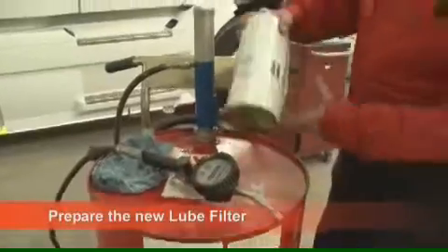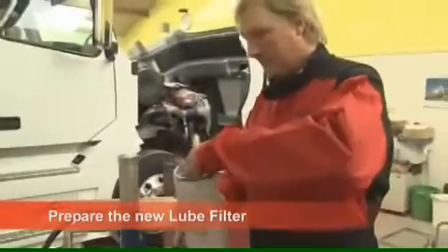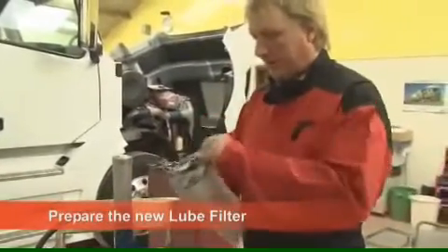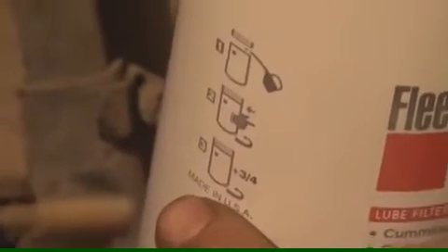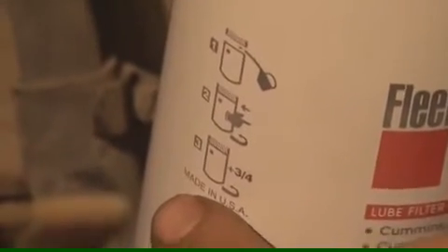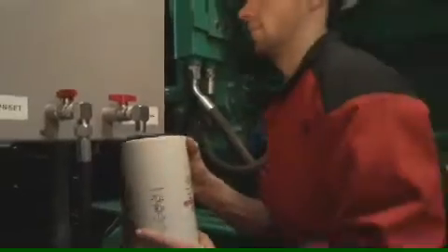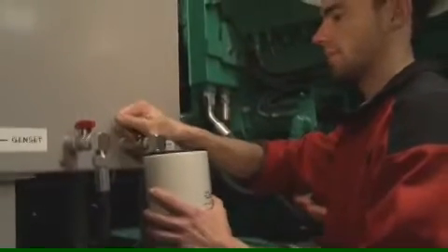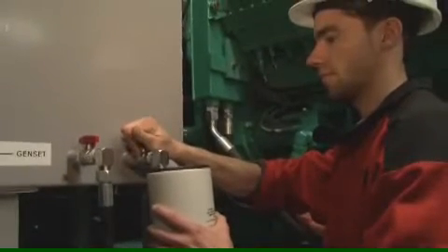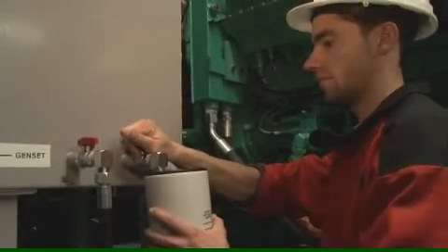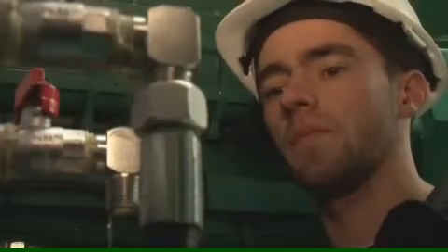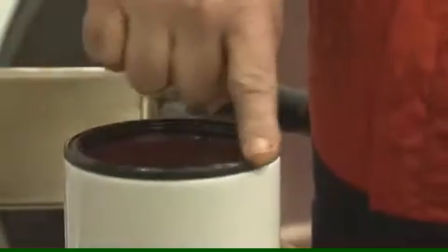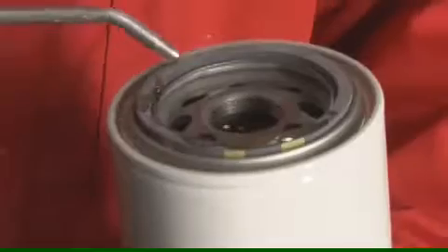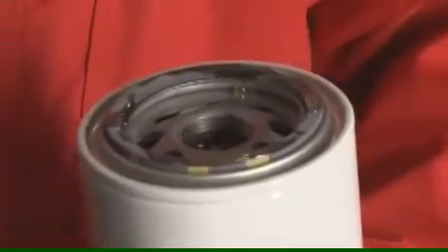Before installing the new lube filter, make sure that any gaskets or seals are present and correctly positioned. Then, look at the installation pictograms on the filter to validate if the filter requires pre-filling. Where the pictogram indicates pre-filling, obtain a sufficient amount of clean lube oil from a reliable source to pre-fill the filter. Pre-fill the filter up to the top. Finally, lubricate all gaskets and seals with clean lube oil.